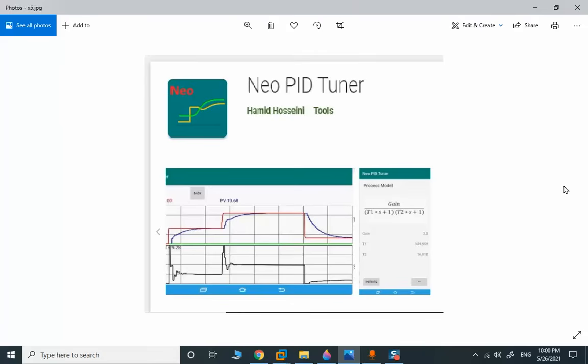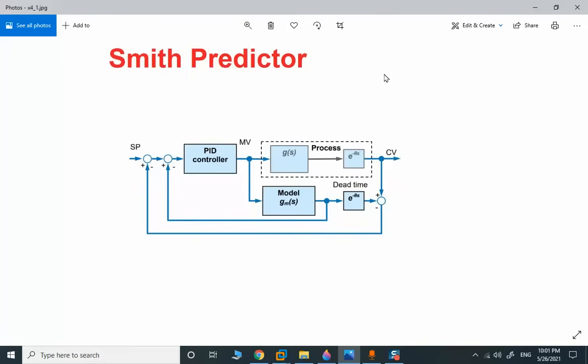It is very easy to implement — the function block called Smith Predictor can be used in Delta V, PCS7, and other platforms. Before that, we need a tool to estimate our process model. One of those offline tools I can introduce is the Neo PID Tuner, an Android application that provides the time constant and gain for any given process model. It can estimate first order, second order, and in some cases high order process models. I will show you how I implemented this Smith Predictor in Delta V and function test it.